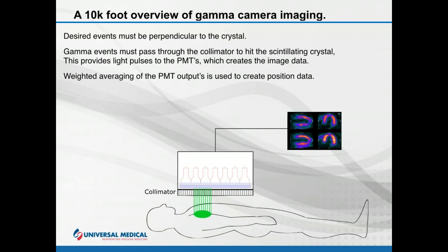We introduce a device called a collimator, which forces all gamma rays to be parallel to each other and perpendicular to the crystal in order to pass through and interact with it. Once a ray hits the crystal, the photomultiplier tubes detect it and use weighted averaging to generate a position — creating an image. The left-hand part of the heart's emissions impact further left on the detector, and the right-hand part is detected by a different portion of the crystal. This is critical in creating an accurate image.